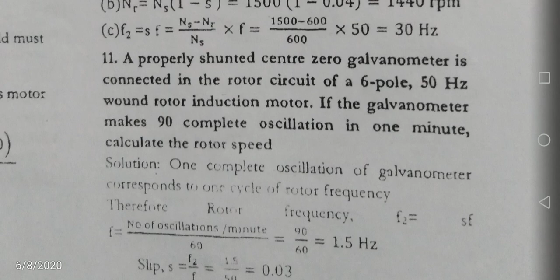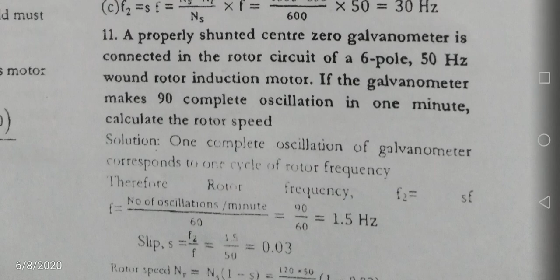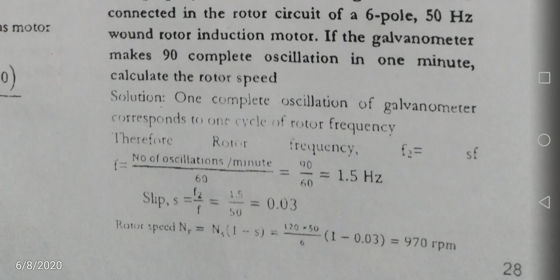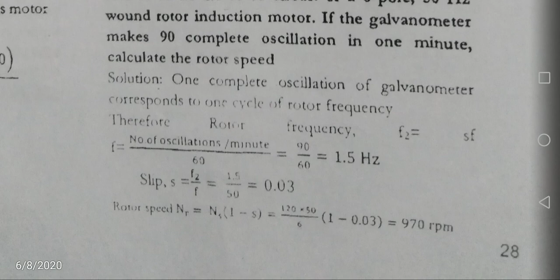A properly shunted centre zero galvanometer is connected in the rotor circuit of a 6-pole 50 Hz wound rotor induction motor. If the galvanometer makes 90 complete oscillations in 1 minute, calculate the rotor speed. Solution: 1 complete oscillation of the galvanometer corresponds to 1 cycle of rotor frequency. Therefore rotor frequency F2 equals SF. The frequency is the number of oscillations per minute by 60, that is 90 by 60, 1.5 Hz. Slip S equals F2 by F, that equals 1.5 by 50, that is 0.03.